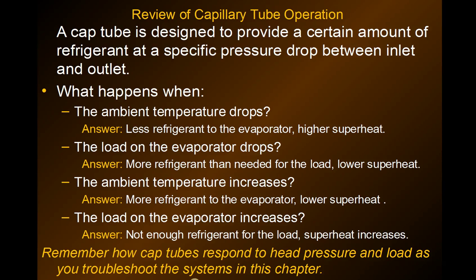Capillary tubes are considerably different than the TXV, so these are some things you need to remember when troubleshooting cap tube systems and how they respond to head pressures and load. A cap tube is designed to provide a certain amount of refrigerant at a specific pressure drop between the inlet and outlet of the cap tube. If the pressure increases at the inlet of a cap tube, there's going to be more refrigerant forced through there.